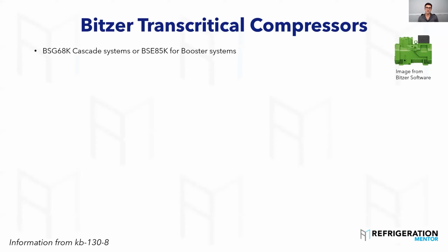The other one's a booster system, where you're doing CO2 on the transcritical side for the medium temp, and you have the low temp CO2. And you're actually pumping, and that low temp compressor is actually discharging into the suction of the medium temp. Depending on how they pipe, but that's really how it works. That's why it's called a booster system. The low temp compressor is pumping into the medium temp system.